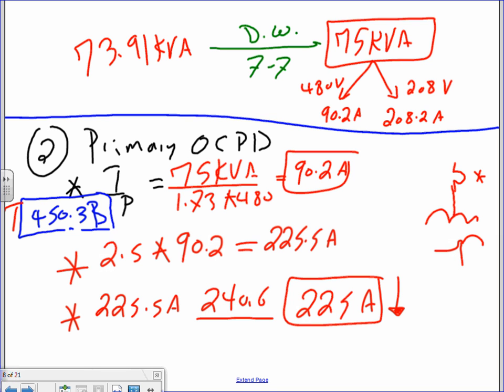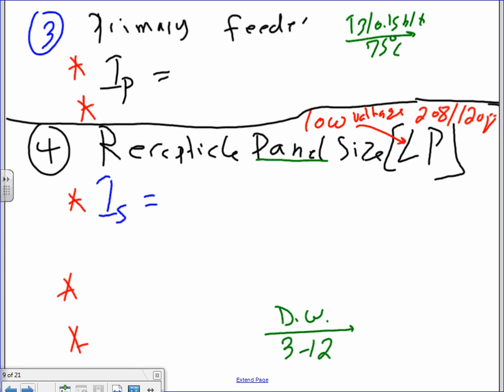So the primary, now what's in it for you, Derek? You're going to go to Revit schedules when we do the schedules in a couple of weeks. Change the overcurrent device that feeds that transformer to 225 if that's the size of your transformer, which most likely is going to be around this size. Next, primary feeder. Matt, you need to give me a few things. What was the primary for this transformer again? Primary current.